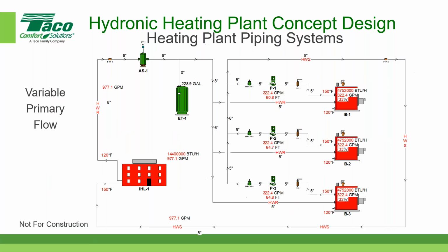Okay, so here is the diagram, and I've got it labeled on the left-hand side here. It's variable primary flow. So in this particular case, every time a boiler fires up, there is a circulating pump that's associated with that boiler. Now, I don't have my pointer tool. Will my cursor work? Yeah, my cursor works. Can you see my cursor, Brett? I can. So here we have a dedicated pump serving a boiler. And in this case, the pump would be variable speed, and you would increase or decrease the speed to match the load that's in your building. And in this case, I'm using the same one that I mentioned in a previous slide, where each boiler is sized for 33%. So as the load increases and decreases, the flow through the boiler increases or decreases.